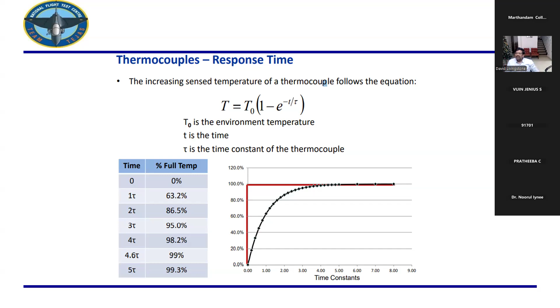So once we were asked to put a thermocouple for a missile firing, to measure the effect on the wing, right, on the belly of the aircraft. But the thermocouple response time is 2 seconds, but the missile will go in 20 milliseconds, 30 milliseconds, right? So it can never pick up that kind of temperature effect on the wing, right? So we need to think of a different way of testing, instrumenting that, right? So this response time is a function of the diameter of the sensor, and it takes time. See, it has to reach 100%, then there is a correct value. It takes some 2 to 3 seconds, right? So if that time is not critical for us, then we can possibly depend on this kind of sensors.